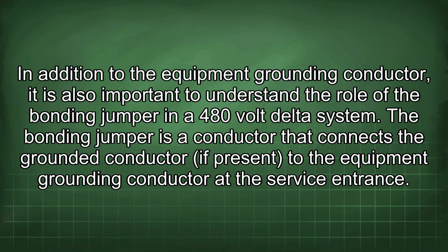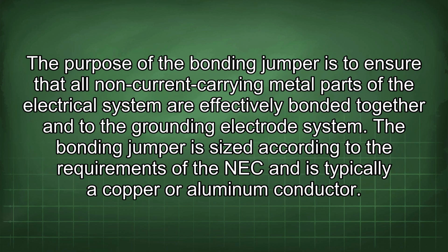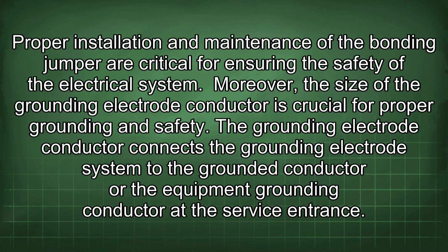The bonding jumper is a conductor that connects the grounded conductor, if present, to the equipment grounding conductor at the service entrance. The purpose of the bonding jumper is to ensure that all non-current carrying metal parts of the electrical system are effectively bonded together and to the grounding electrode system. The bonding jumper is sized according to the requirements of the NEC and is typically a copper or aluminum conductor. Proper installation and maintenance of the bonding jumper are critical for ensuring the safety of the electrical system.